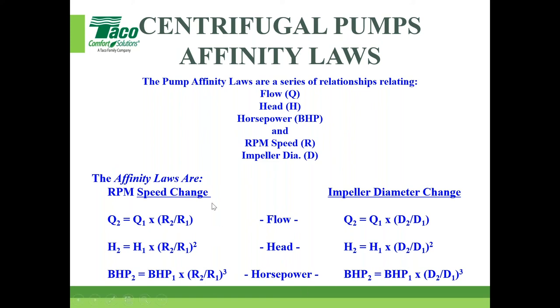It's pretty straightforward. On the left-hand side, it's speed change. Flow rate is R2 over R1, head is squared and horsepower is cubed. For impeller diameter change, instead of speed change, it's impeller diameter change to get you the new answers here. We're touching upon this; I wanted to at least expose you to it. I'm not going to go through any calculations.